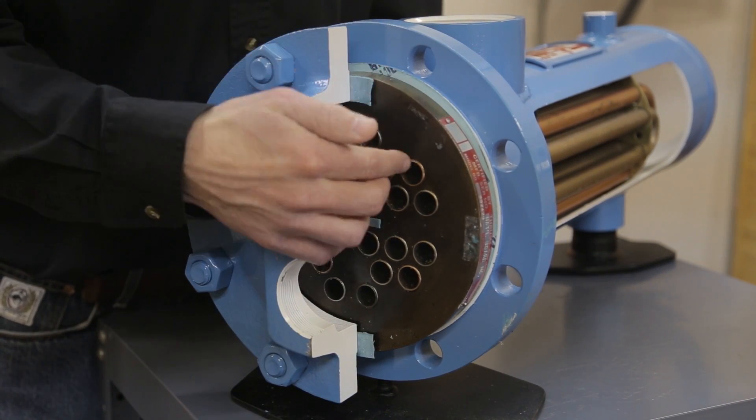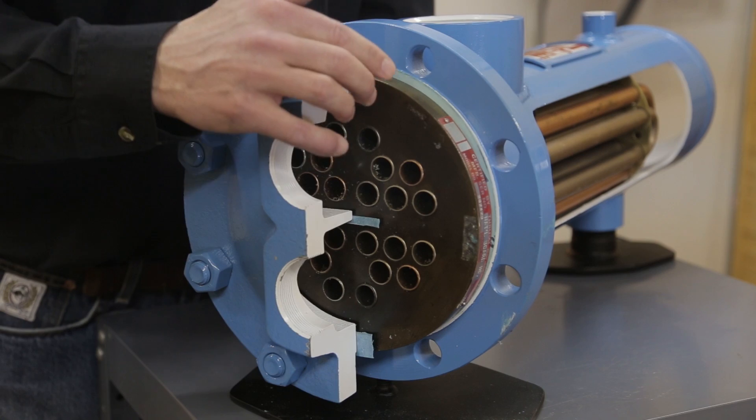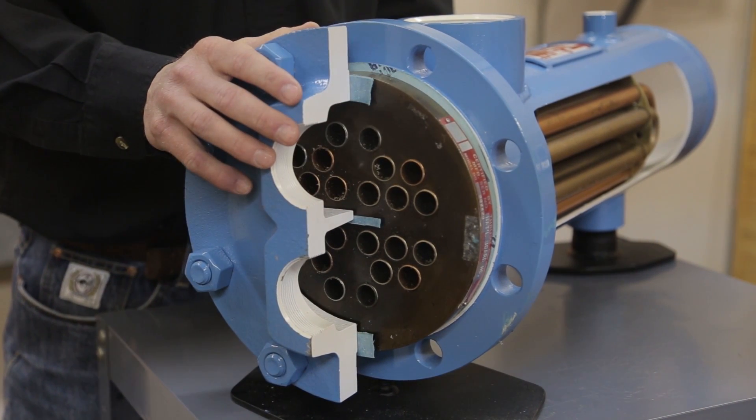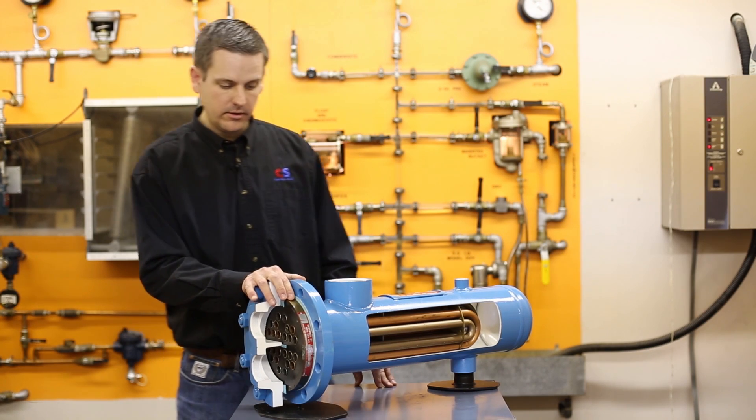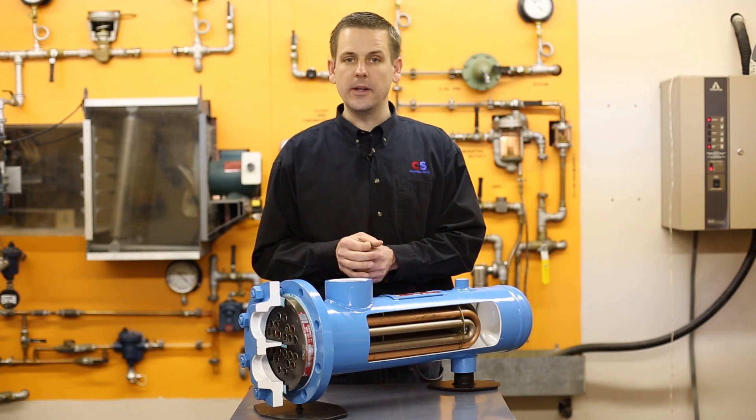In this particular case, this is a single tube sheet. Now, in many states we have what we call double wall tubes where these tubes are actually a tube in a tube. When that's the case, we actually have two tube sheets stacked together.